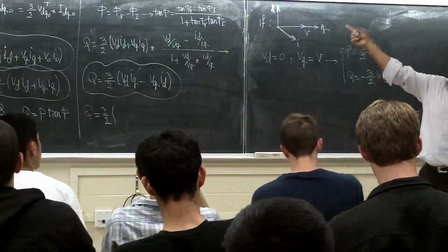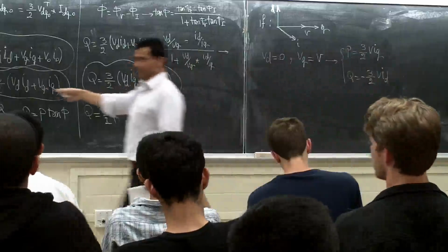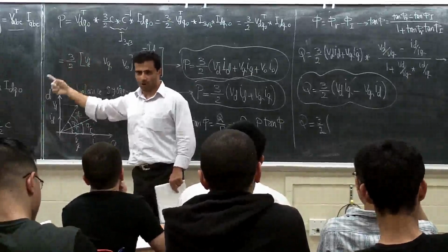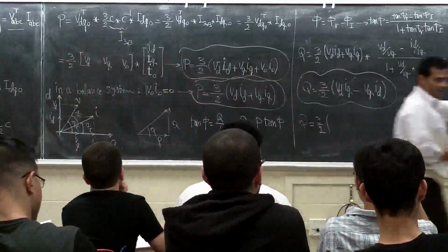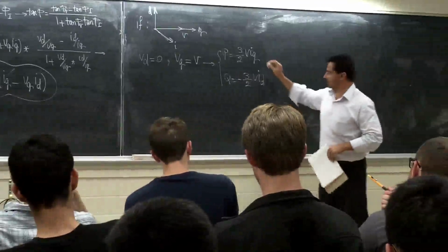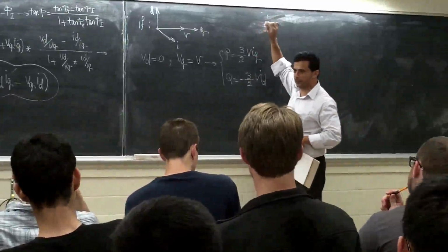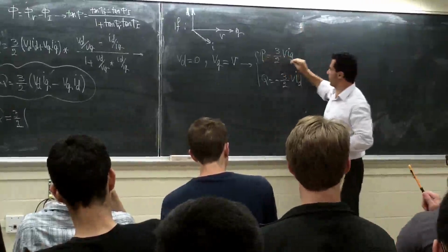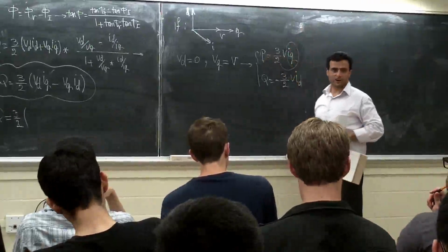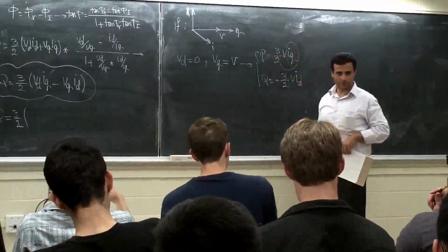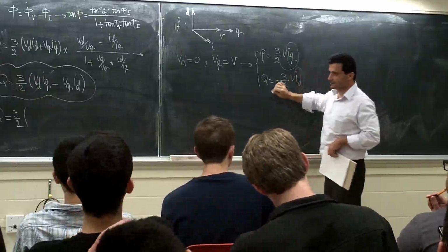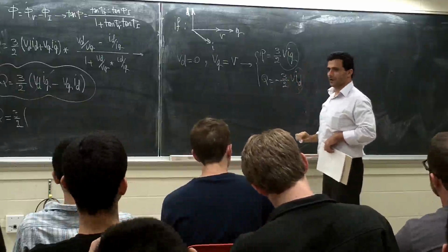The amplitude of the voltage, the ABC voltage, either the RMS or the maximum, depending on what you select. This is constant. I'm connected to a grid, 120 volts, 480 volts, something like that. I can control active power with Iq. If I control my Iq, I'm controlling my active power. If I control my Id, I'm controlling my reactive power.